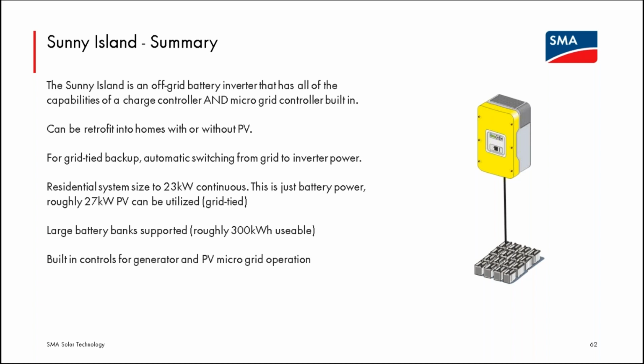I was unaware of that. I'm assuming there's a bat fan that was a default setting for one of the relays, so that if you hit a certain charge cycle and you had a lead acid battery bank where there could be quite a bit of hydrogen being generated during this charge cycle, you could trigger a fan to come on automatically when that part of the charge cycle was entered. If that's the question, I was unaware that choice was actually taken away. So I can follow up on that.